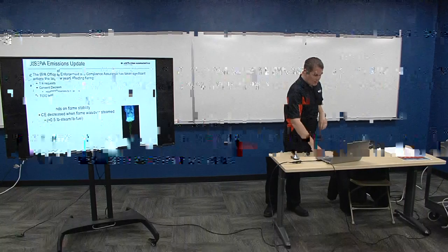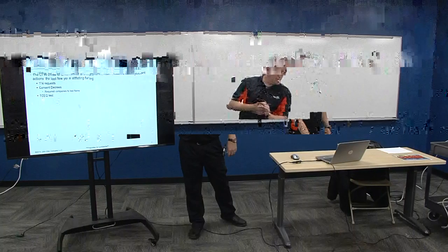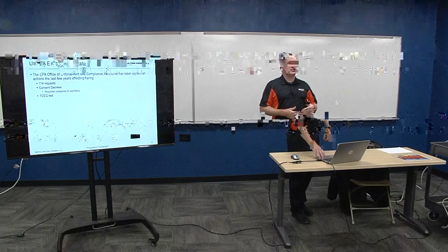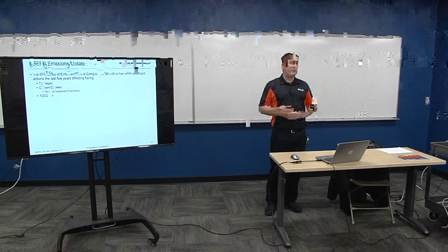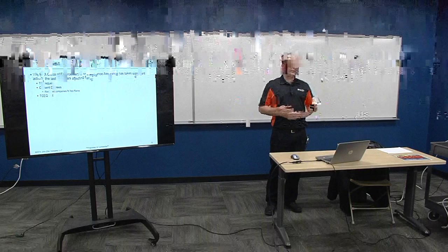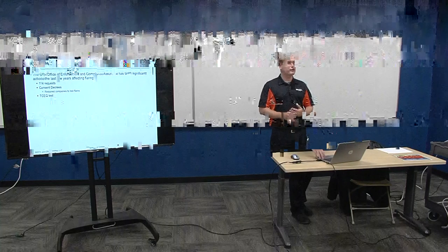So again, 1985, we still knew oversteaming was an issue. But the EPA, in their first issuance of 40 CFR 60.18, made some requirements to the system where they basically just looked at the BTU level of the gas going to the flare. And so a lot of people made sure that the BTU of the gas going to the flare was within the regulations. But it allowed for improper operation.